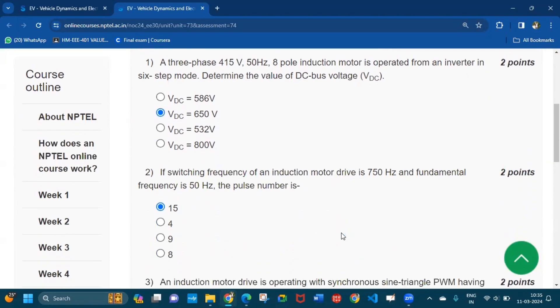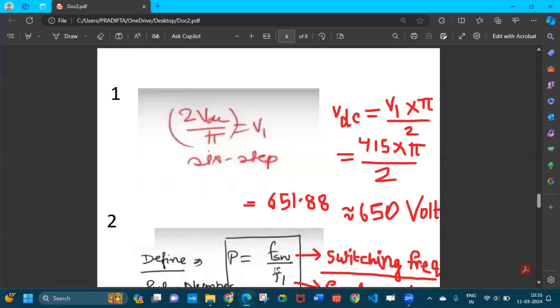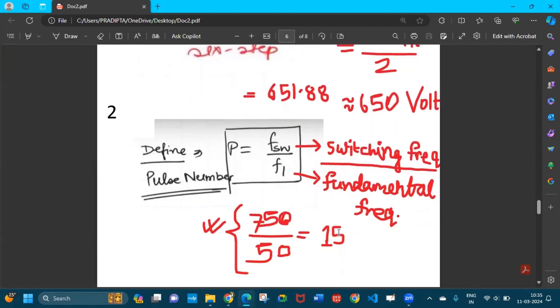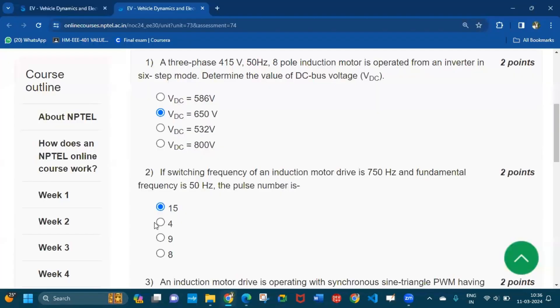Coming to question number two: if the switching frequency of an induction motor drive is 750 hertz and the fundamental frequency is 50 hertz, what is the pulse number? The pulse number is equal to fsw / f1, where fsw is the switching frequency and f1 is the fundamental frequency. With 750 hertz switching frequency and 50 hertz fundamental frequency, the pulse number is 15 — option one is the answer.